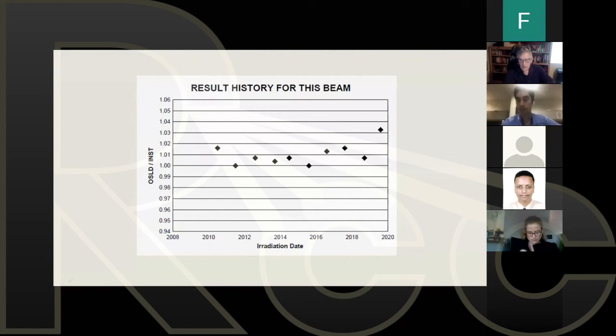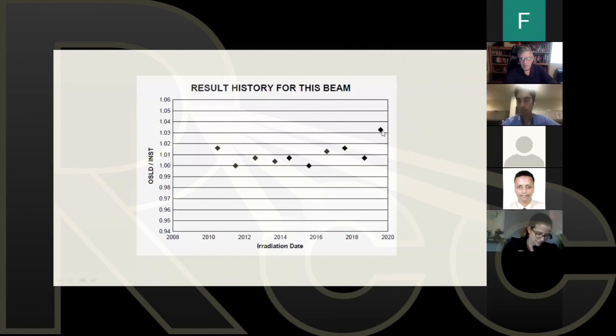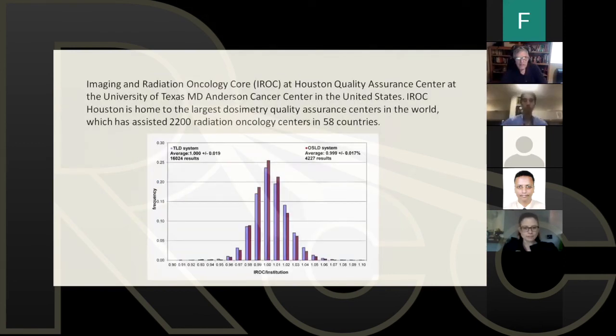The laboratory that I use at MD Anderson in Texas says that the result is accurate and within 5%. So any reading within 5%, they consider that to be a pass. 5% is a little too much for me. I start to get a little nervous at what you see here, 3%. And maybe I want to investigate that a little bit more, because the TLDs tend to be very, very accurate. But because of all of their uncertainty factors they've analyzed, they tell you that you can consider a pass within 5%. The IROC, Imaging and Radiation Oncology Core, formerly the Radiological Physics Center, RPC, at MD Anderson, published this a little while ago.